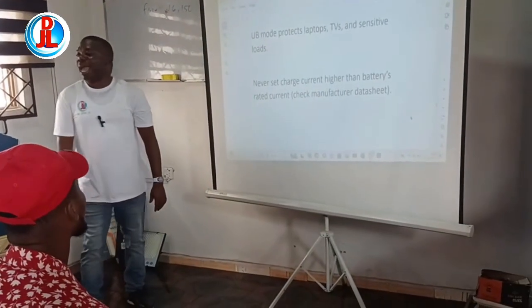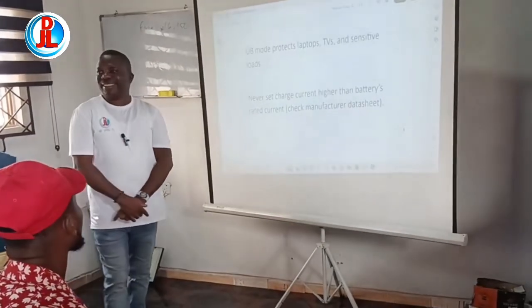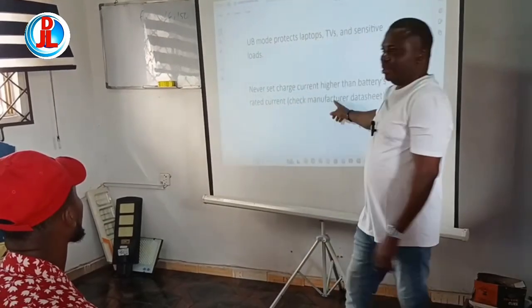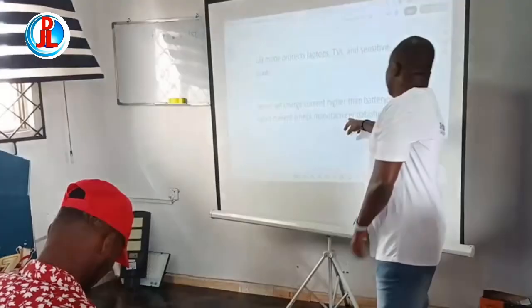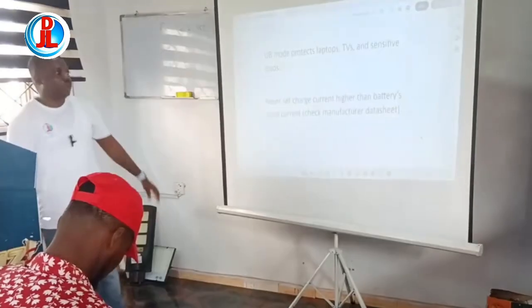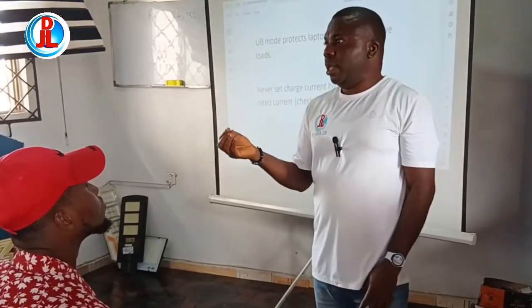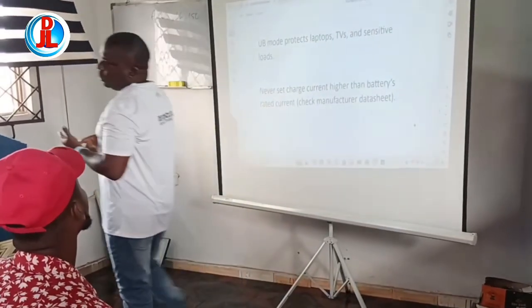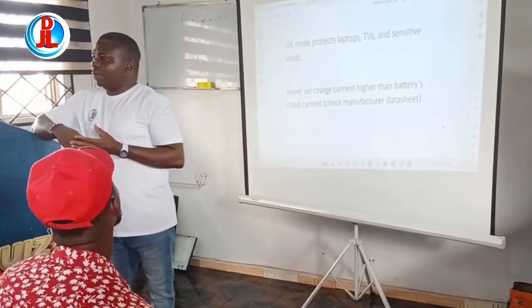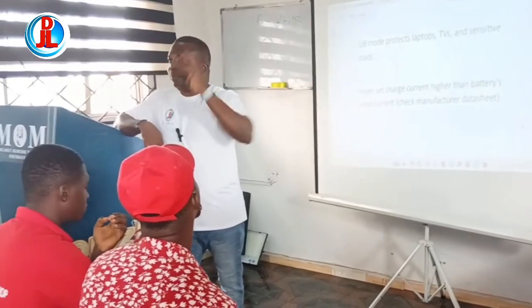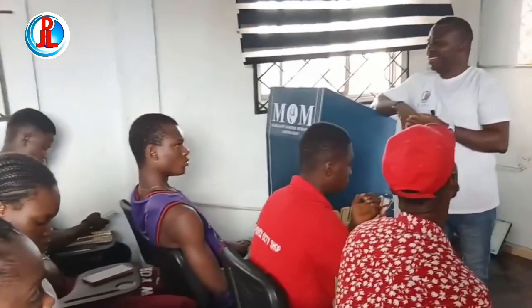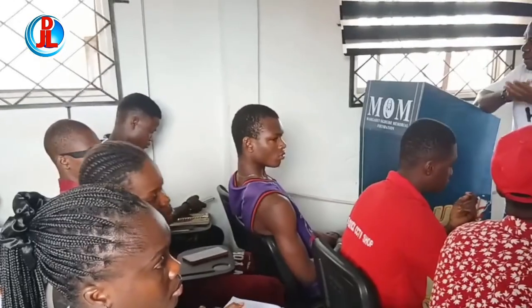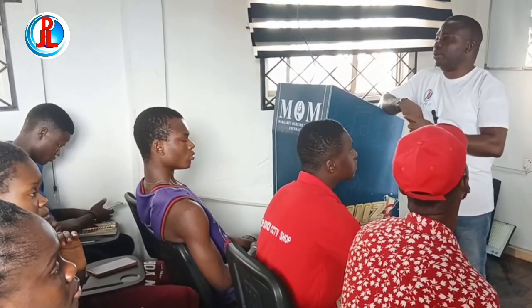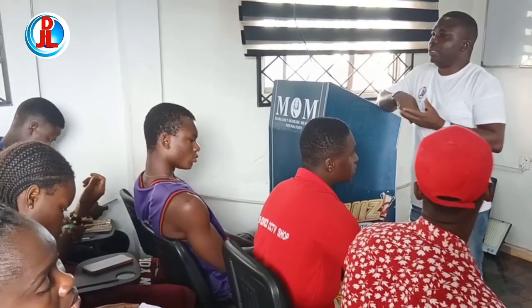Never set charging current higher than the battery's rating. Go and check the battery data sheet. If I have a battery manual, I will see the charging current specified for that battery. Pick up a manual. Some of us don't read. If you finish the manual of a battery, I swear you'll be so good. If you finish the manual of this inverter, I need a manager to scan the manual and base it on the system. Manual of battery and manual of this thing. So let everybody read. Now, this battery has a data sheet.